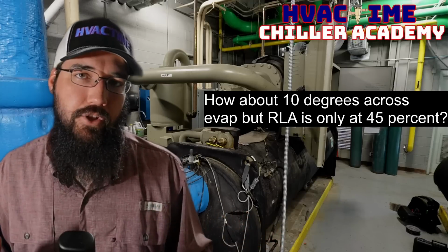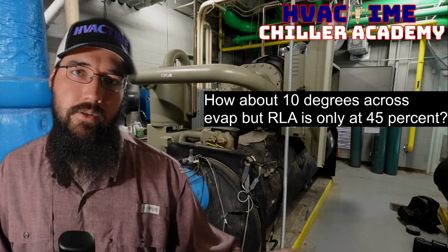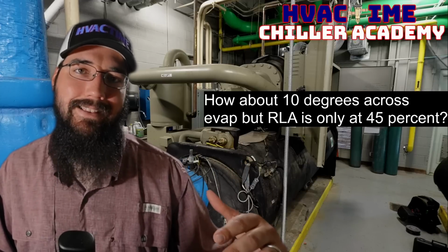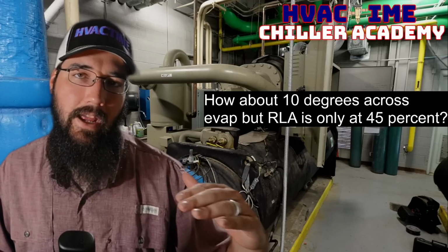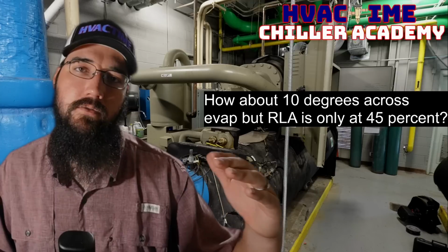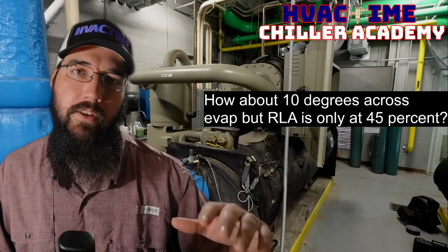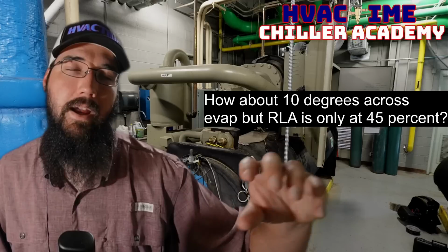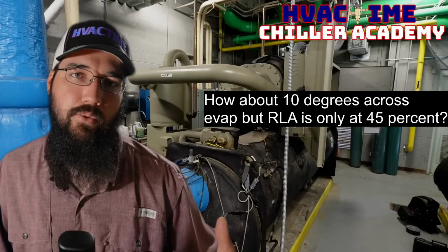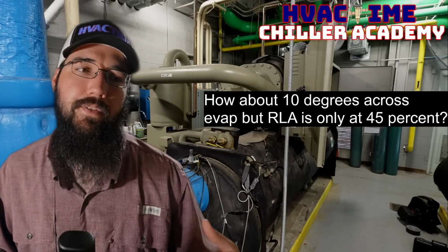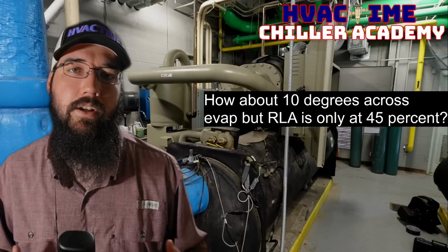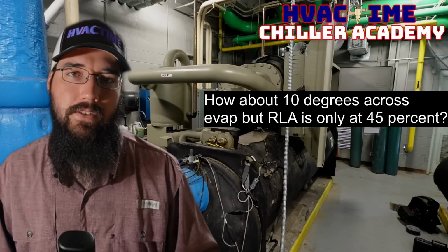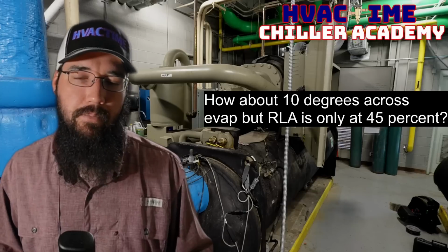for a chiller design for a 10 degree drop across the evaporator, if I am operating at that and I've got at least an 8 degree or more difference, like I'm making set point and my entering water is high enough to be 8 to 10 degrees, or at least 8 degrees above that, then I consider I've got a pretty decent load, and I should be able to get a pretty good analysis of how the chiller is operating.